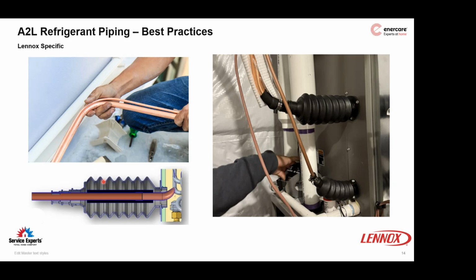So Goodman's point of view is, if you have a joint in your piping or several joints in your piping, they need to be made accessible or left accessible. The oil that's in the systems is going to be the same or very similar to what 410A is being pushed with. So the oils are very similar. Still, all the manufacturers I read suggest flushing the system, regardless of R22 or 410A, so that your oil has been removed if you had to reuse some of the line set. Hopefully you won't have to. Ideally, we would like to have a new line set put in.